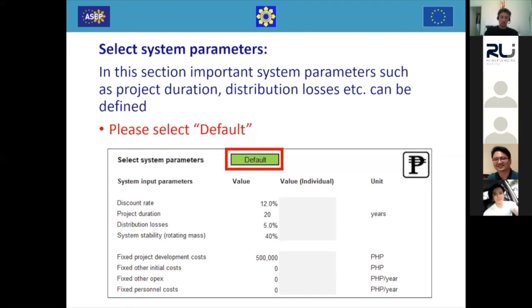For example, if there is a sudden change in demand or a sudden change in renewable energy generation due to clouds or due to less wind, for example. But now for the solar system, it would be cloudy weather or maybe a failure in the system. Then the diesel generator can quickly jump in and keep the frequency of the AC grid in a stable operating state. But of course, also a hydro power plant could provide this system stability, or also the modern inverters of batteries. They can emulate such a rotating mass and also provide the system stability. So if there is enough battery capacity, then the diesel generator can be turned off. So this value can, of course, also be adapted individually according to local site-specific conditions.